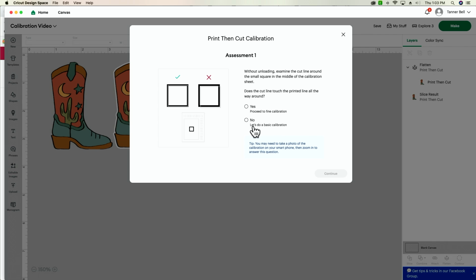It's going to be the same process as a fine calibration, but your machine will do a basic calibration first, and then you are going to want to go back and do a fine calibration. Now, for today, I'm going to click yes because I want to do a fine calibration because our machine is not this off. But like I said, if yours is, select no, do a basic calibration first, and then come back and do a fine.